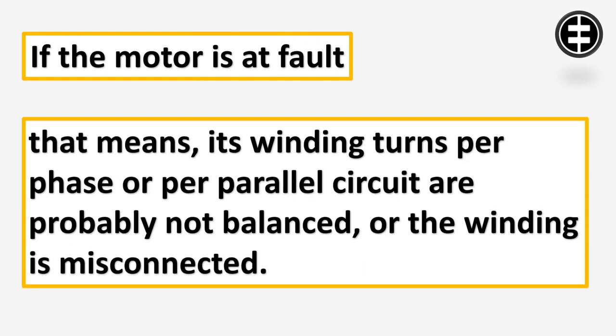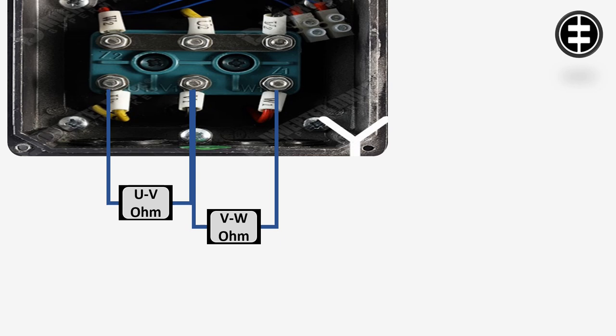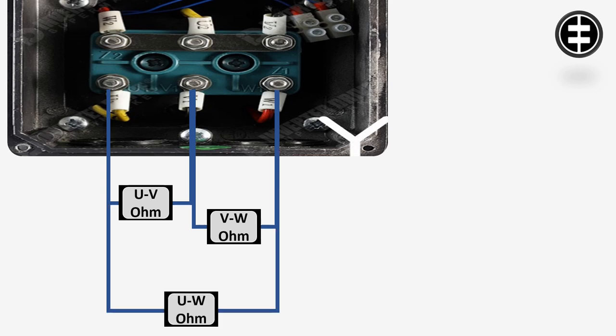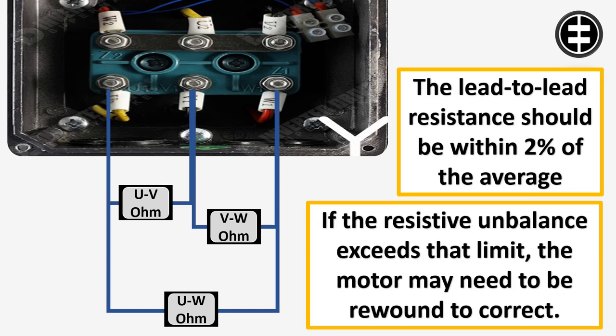Measuring the lead-to-lead resistance with a digital low resistance ohm meter may detect unequal turns. The lead-to-lead resistance should be within 2% of the average. If the resistive unbalance exceeds that limit, the motor may need to be rewound to correct the problem.